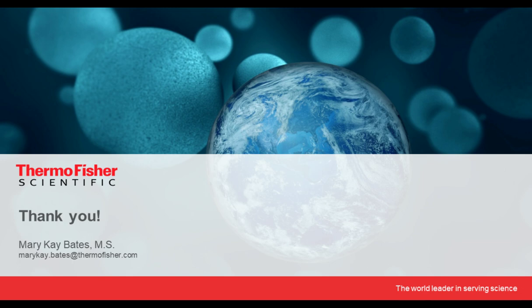Thank you for that. And here's our next question. It's 2 parts. What kind of device do you recommend to use to measure CO2 level? And if the CO2 level was wrong, is it easy to modify CO2 levels by ourselves? Depending on the incubator, there should be instructions in the user manual for modifying the calibration, or basically the offset of the CO2 sensor. For replacement of the sensor, I would recommend a factory-trained service specialist. And I hope I answered the question. If I didn't quite answer that correctly, let me know.